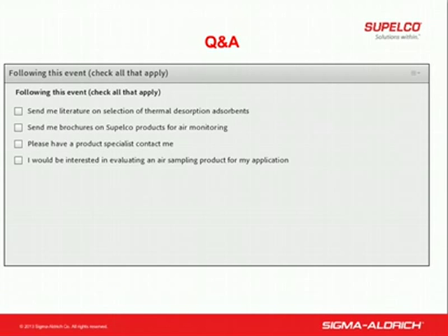Okay. In which applications is it best to select a glass thermal desorption tube over stainless steel? I personally like glass because I like to see what's going on in a tube. I can tell if there's any channeling happening. So I don't have a specific application chemically, but when we're going out taking important samples, it's nice to see what that tube looks like before and after sampling.